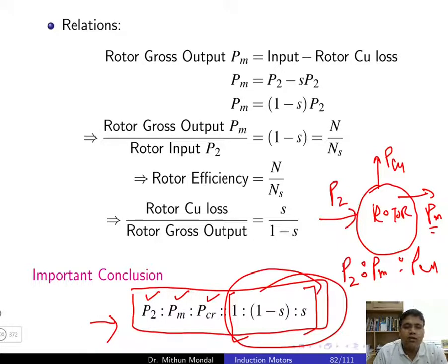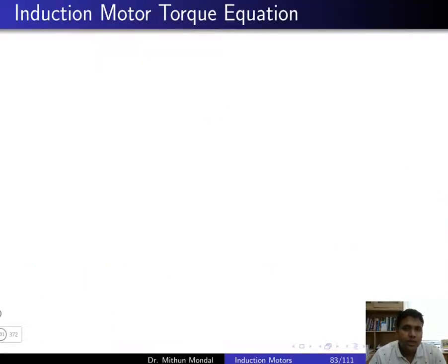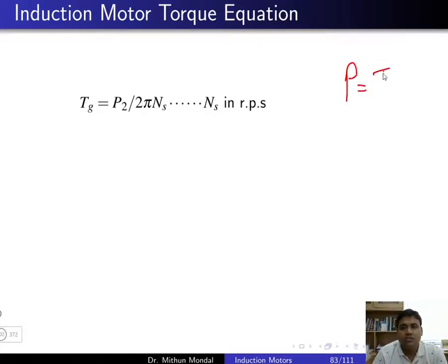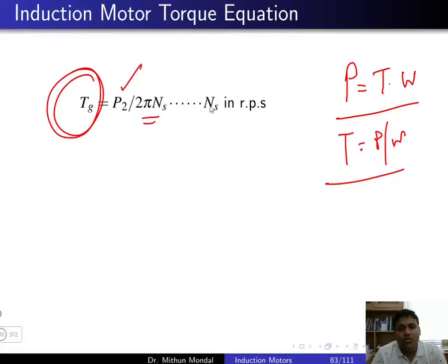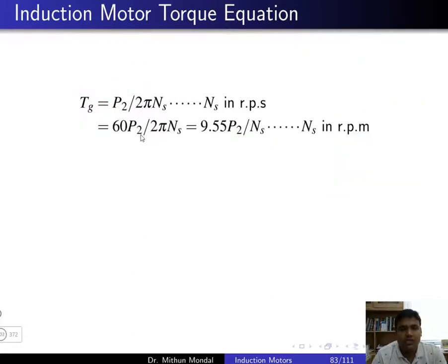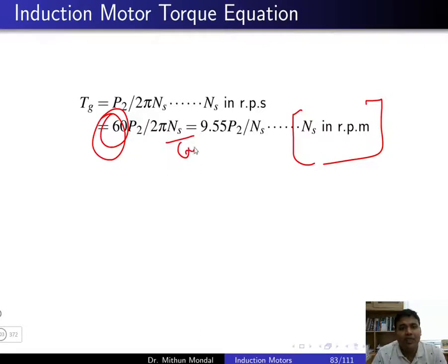For the induction motor torque equation, using power = torque × omega: gross torque Tg = P2 / (2π × Ns) when Ns is in RPS. When Ns is in RPM, the equation becomes Tg = 9.55 × P2 / Ns, since dividing by 60 brings 60 into the numerator.